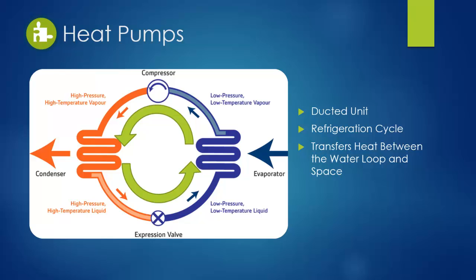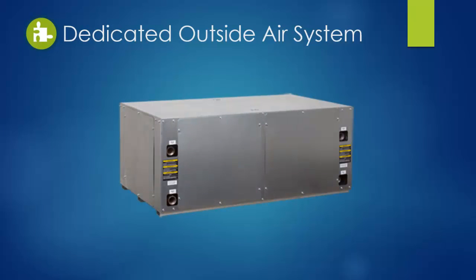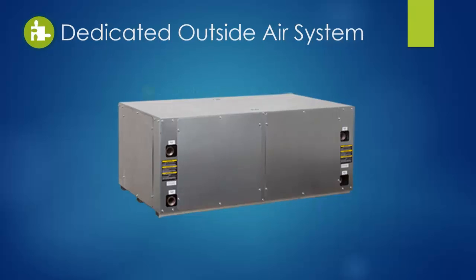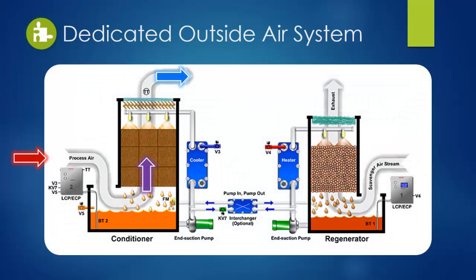heating and cooling. Component 4 is a dedicated outside air system, or DOAS, which will supply the building with makeup air. The DOAS for the building will be a heat pump with electric preheat to ensure the minimum entering air temperature recommended by the manufacturer. The DOAS will also utilize a desiccant heat exchanger located on the roof to recover heat from the exhausted air.